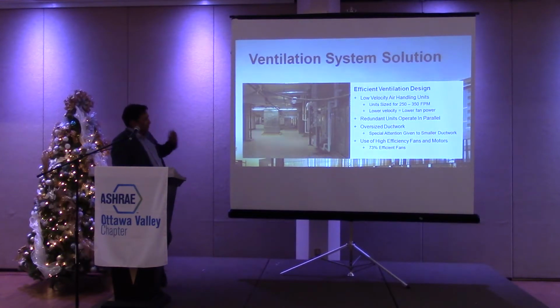So the efficient ventilation system design was focused on reducing pressure drop. And the way that we did that was we oversized our air handling units. It sounds extremely simple, but that's actually what we did. We reduced the velocity through the air handling units to a range of 250 feet per minute to 350 feet per minute, and lower velocities lead to lower fan power.